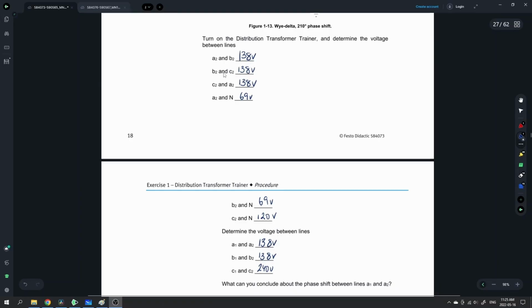And then 138 from B2 to C2, 138 from C2 to A2. From A to neutral we saw 69, B to neutral we saw 69, and from C to neutral we're seeing root 3 of 69. So 69 volts times 1.732 gives us 120 volts on the C phase.